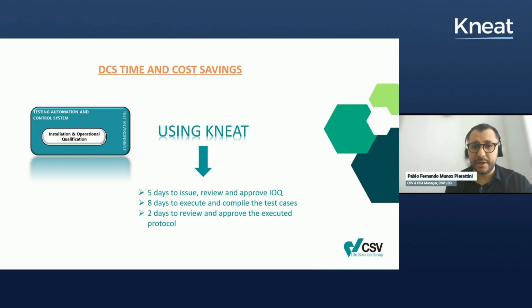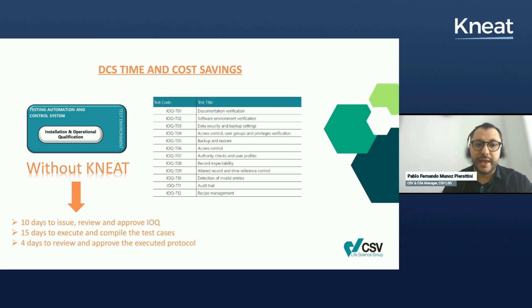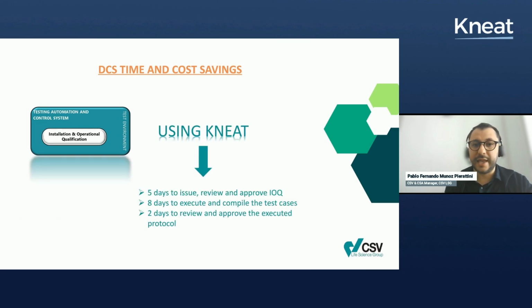Using Kneat, it is the same exercise but without the paper-based compilation, and we have just 8 days to execute and compile the test cases. If we compare the 15 days and 8 days, we save a lot of time, and 5 days to issue, review, and approve the installation and operational qualification protocol. For the review and approval, we just need 2 days because you have all the screenshots and documents in Kneat, so you don't need to search the paper-based protocol for your screenshots, comments, notes, and deviations, because you have all the information in a unique system.